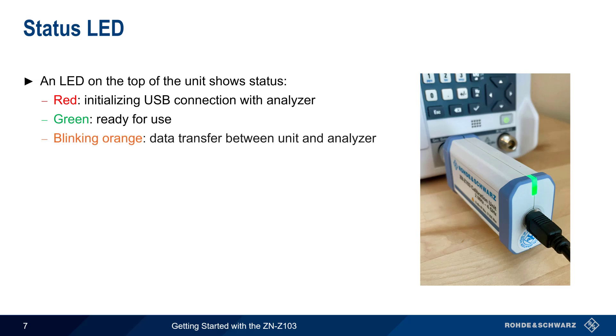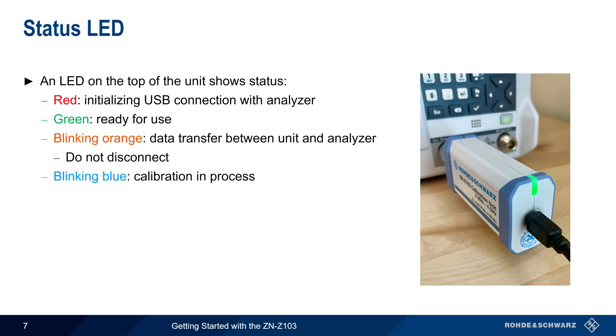A blinking orange LED indicates that data is being transferred between the unit and the analyzer. During this time, the unit should not be disconnected. Finally, a blinking blue LED means that calibration is in process.